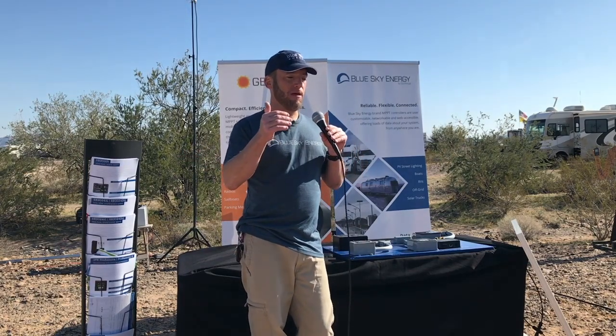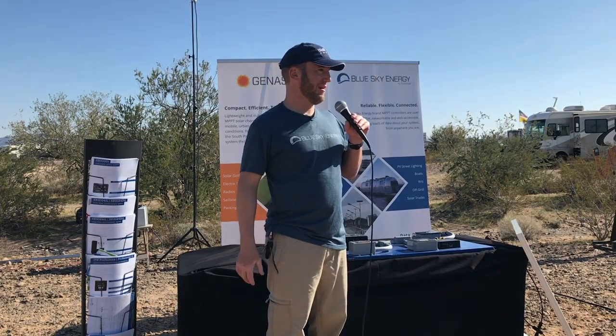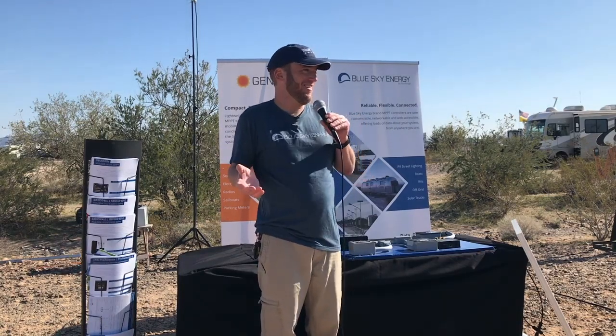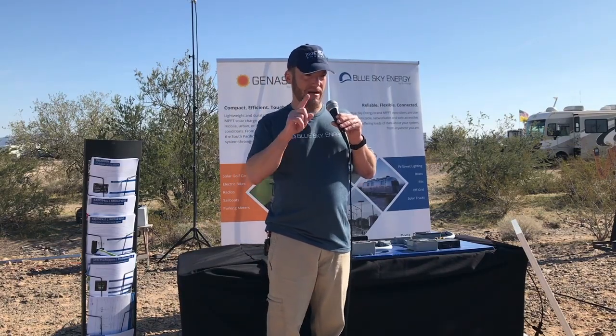He's asking how to keep this load dump from occurring. You could have a DC breaker on your PV input, so you can switch off your solar, assuming you're putting it in storage during the daytime. Or you could put it in storage at night, and as long as you flip the battery disconnect switch when the sun's down, I don't care - the controller's not actively charging. But if you're trying to put it in storage during the daytime while your solar's actively charging, a breaker would be beneficial.